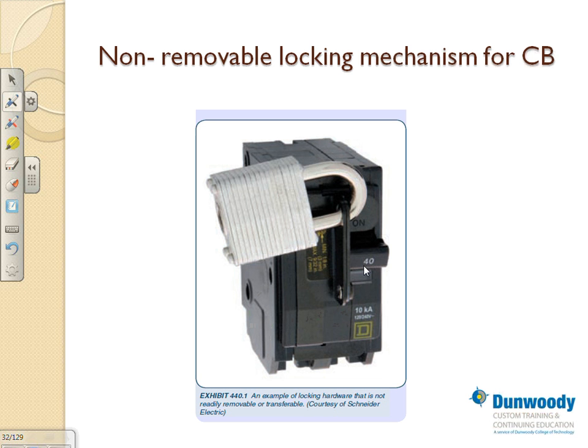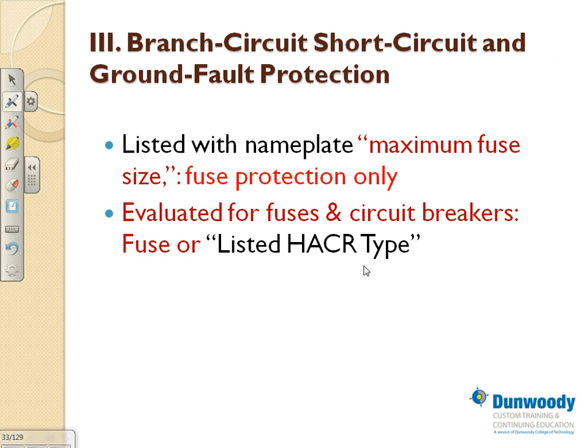So what a lot of us do is have a portable disconnect, right? You guys use them. If I want to change this receptacle, I turn the circuit breaker off and lock it with my little lock, a portable one on the circuit breaker, so nobody can energize it. Come over here and change the receptacle. That doesn't apply to an air handling unit. For an air handling unit, you have to go to the disconnect. If it's right next to it, work on it, lock it, tag it. And the locking mechanism has to be in place regardless of the lock being on it or not. If that makes sense.